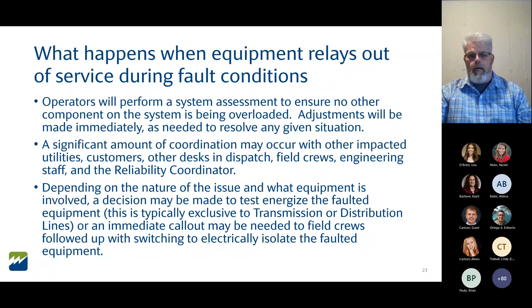It depends on the type of relay targets we see too. It depends what tripped it. For example, on a transformer that relayed on differential, after we inspect it, we may be able to test it. But a transformer that relays on a sudden pressure relay, we won't be able to test it. We're going to have to do some actual tests on the equipment before we can put it back in service. So there's a whole bunch that goes into when equipment trips on a protective relay operation.